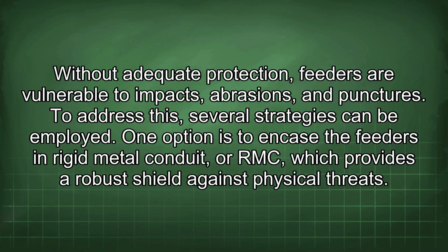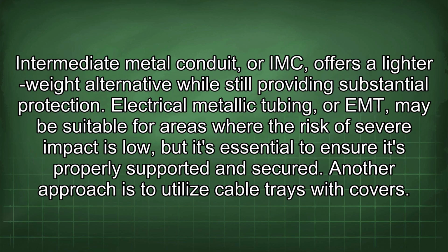One option is to encase the feeders in rigid metal conduit, or RMC, which provides a robust shield against physical threats. Intermediate metal conduit, or IMC, offers a lighter weight alternative while still providing substantial protection. Electrical metallic tubing, or EMT, may be suitable for areas where the risk of severe impact is low, but it's essential to ensure it's properly supported and secured.